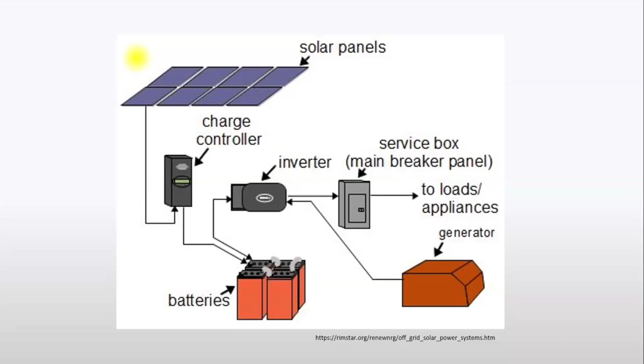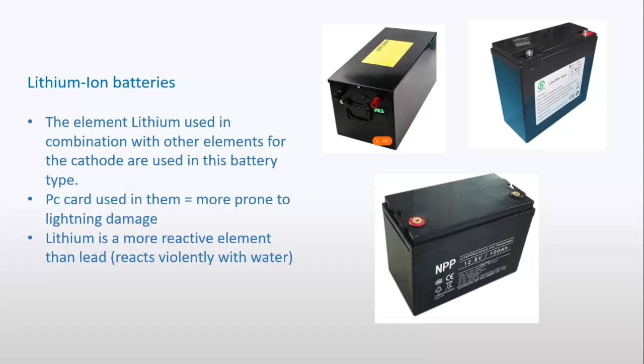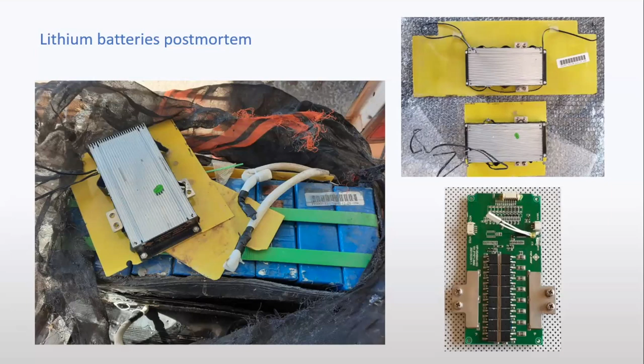So lithium batteries, like I said, are not as easily identifiable. What we've also encountered is lithium batteries don't look like lithium batteries. Some of them actually look like the normal gel type batteries we used to see, especially in motor vehicles. In addition, they have a PCB in them, or most of them should have a battery monitoring system, and that is also very prone to lightning damage. We've seen this a lot. So that's what your lithium battery would look like after a kind of autopsy on it, and that would be the electronics unit usually built into good quality lithium batteries as a measure to control their charge, etc.